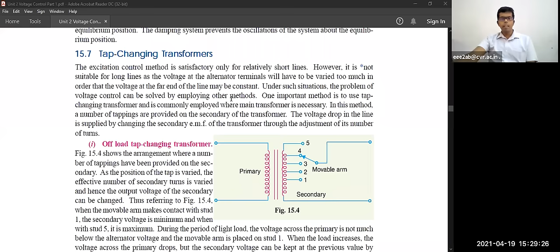Okay, so if you see, this is the off-load tap changing transformer. I think transformers you already studied. So what is the usage of the transformer? The transformer is a device which converts one form of the voltage into another form of the voltage without changing the frequency. So frequency is maintained constant. Only the voltage can be stepped up or stepped down. Sometimes in a generating station, it is stepped up. Why? Because it has to travel a very long distance, 300 kilometers, 400 kilometers. It has to reach your load centers and nearby distribution systems. So in that scenario, we go for a step-up transformer. Sometimes we go for a step-down transformer. A step-down transformer you'll find near your homes, that is your pole-mounted transformer. That is a step-down transformer, 11 kV to 415 volts.